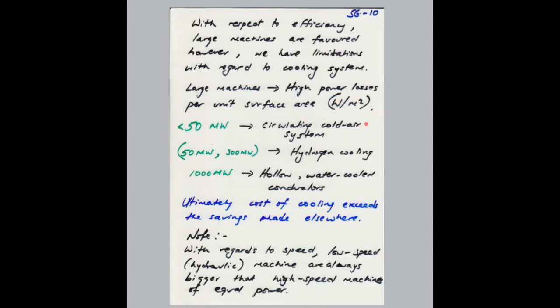If your machine is rated below 50 megawatt, we employ what we call circulating cold air system. If it's rated between 50 megawatt to 300 megawatt, you can use hydrogen cooling. And if you are in the range of 1000 megawatt, you require hollow water-cooled conductors. So as you increase the size, you can see the system for the cooling gets more expensive, and so ultimately the cost of the cooling exceeds the savings made elsewhere, right?